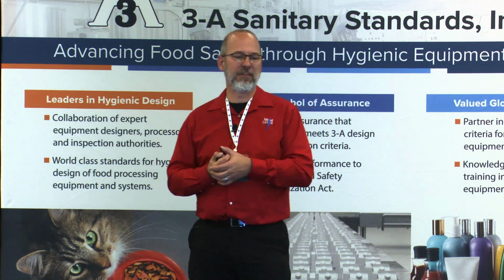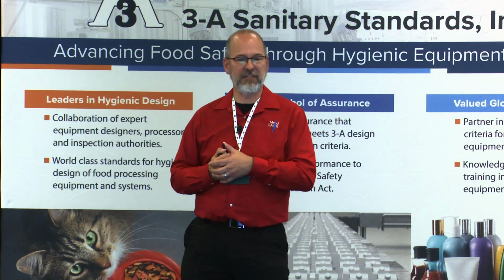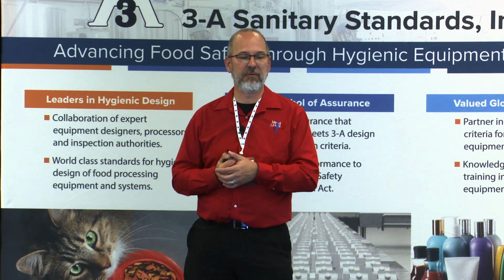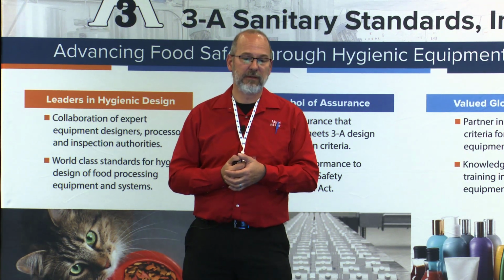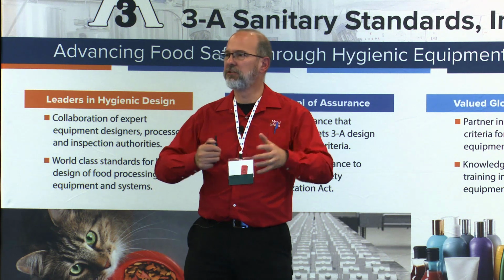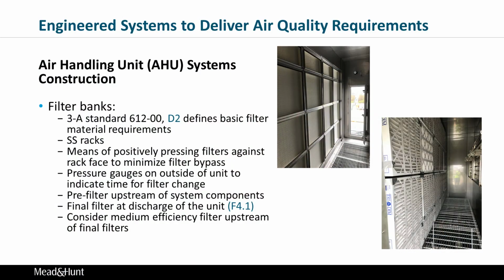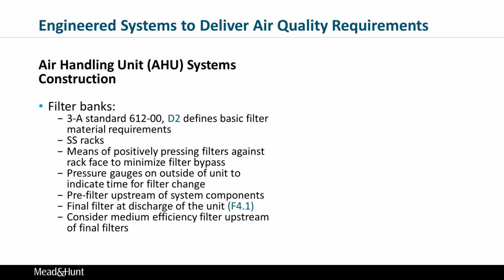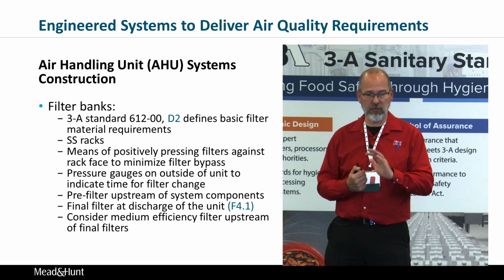Filters. The 3A standard 612 section D2 basically defines basic filter requirements. So I'm not going to go into a lot of detail there, because you can go there and see for yourself. But I also make sure when I specify these air handlers that they have stainless steel racks. I make sure that our specifications for the units require positive fastening of the filter banks, or the filters to the filter frame, so there's no air bypass.